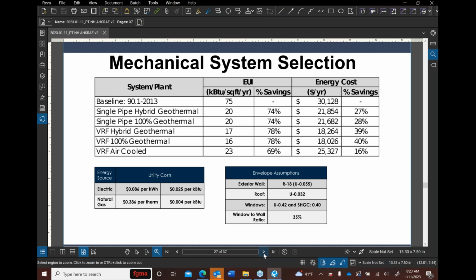So we wanted to make sure we were looking at a bunch of different system options. We looked at the baseline code system, which is a pretty traditional boiler, chiller, unit ventilator system. We looked at geothermal. There was an adjacent school district that utilized a single pipe geothermal system, but that wasn't our highest recommendation. We typically design 2-pipe geothermal systems, but since the adjacent district did a single pipe, we wanted to at least look at that for them.